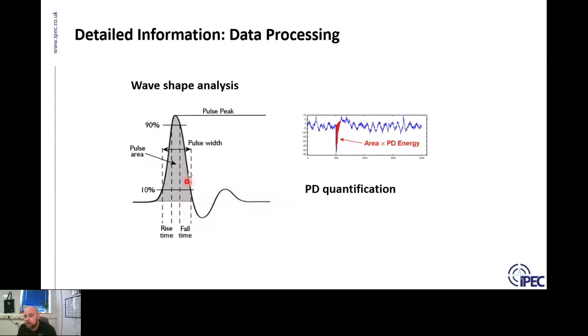Depending on where the PDs come from - so if the PDs come from an underground cable, travel two kilometers, likely it will be of a much lower frequency than it would be of switchgear. Switchgear PD is much closer and so it's going to be a higher frequency. So we're then able to quantify the PD. Our system has measured the rise time, the fall time, the pulse width, the pulse height of the individual PD.